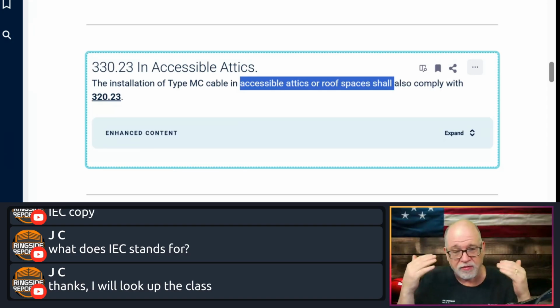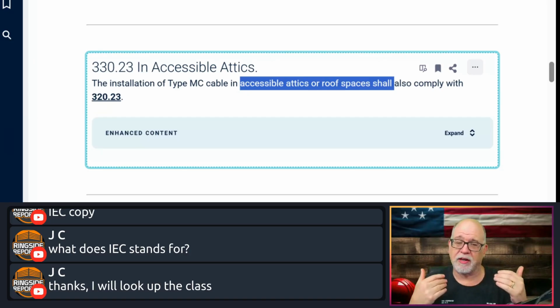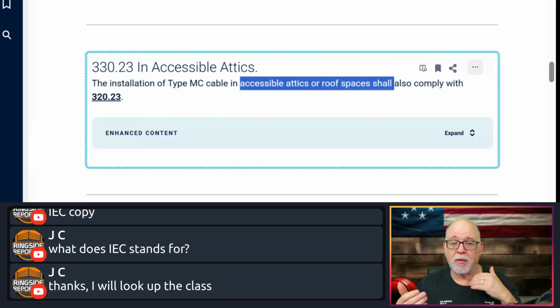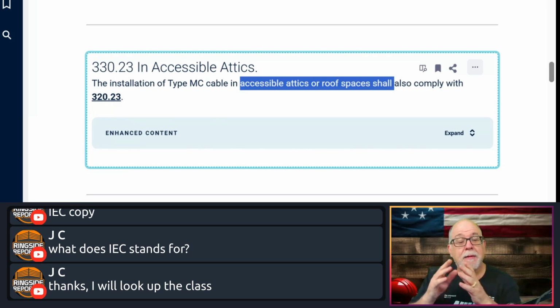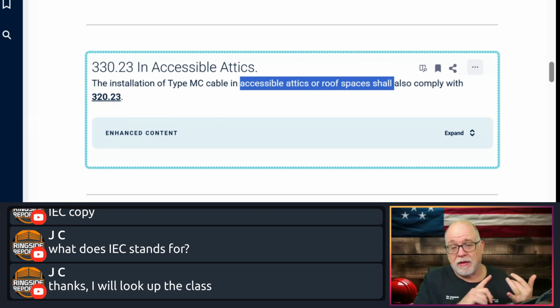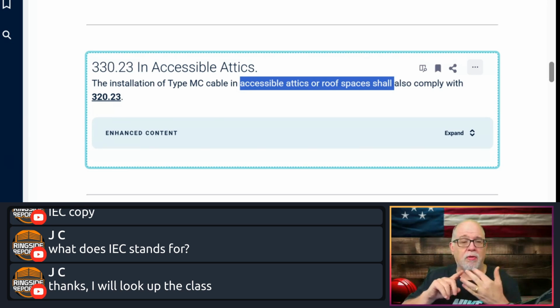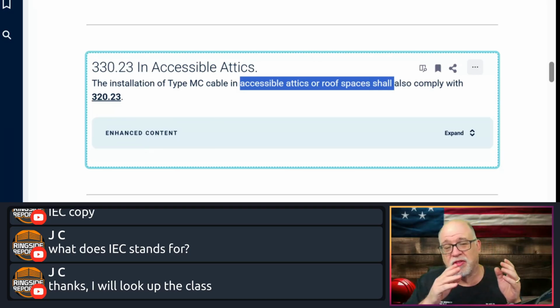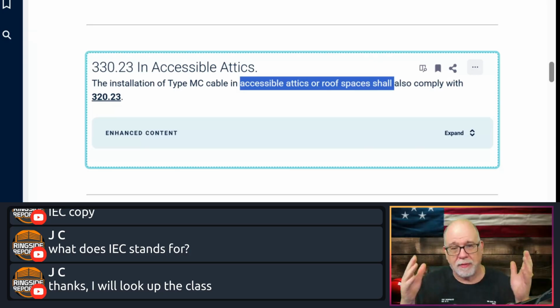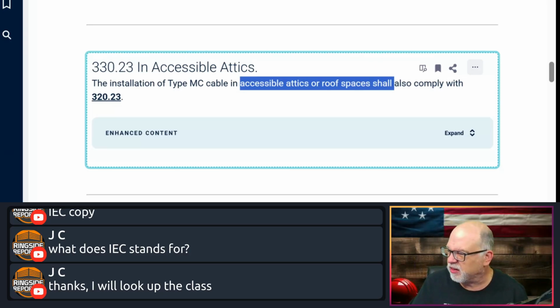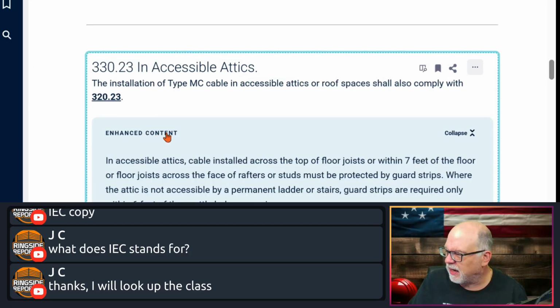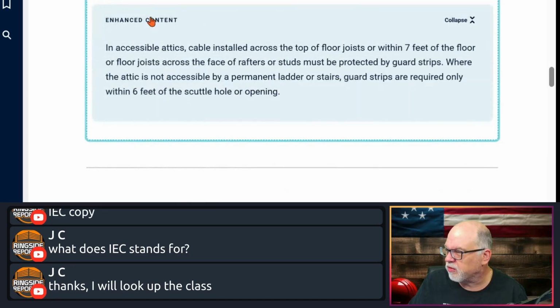The protection of those cables is going to depend on whether you have a scuttle hole or permanent stairs. So go read 320.23, but it's germane to not only AC cable, but also MC cable and non-metallic sheath cable. All of them reference 320.23. Just because you think it's AC, it is germane to all of those when it's referenced. And I don't know that enhanced shows a picture. No, it doesn't show a picture.